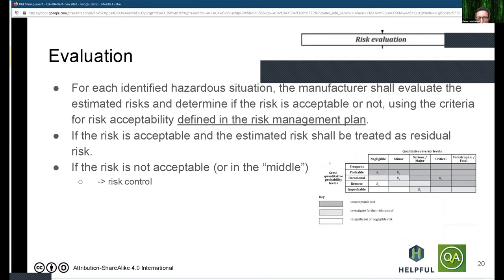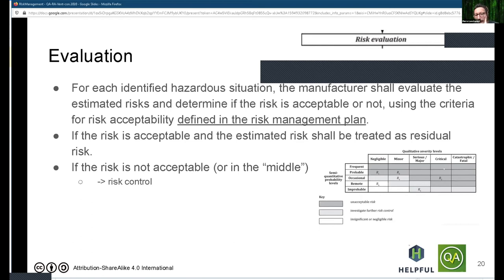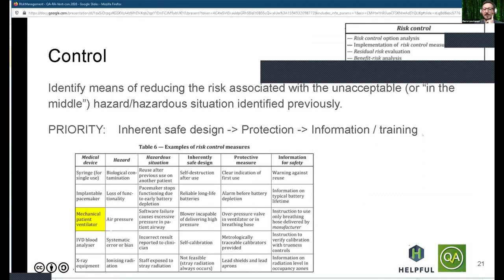Evaluation is the comparison to the risk acceptability criteria you established earlier in the plan. Practically, this means drawing a risk matrix table with as many degrees as you want, identifying the dark area — risks that are severe and probable — as opposed to risks that are improbable and negligible. You define two or three areas of non-acceptable in the top right versus acceptable in the bottom left. Whatever ends up in the top-right area must be mitigated by risk controls to lower it into the acceptable region.